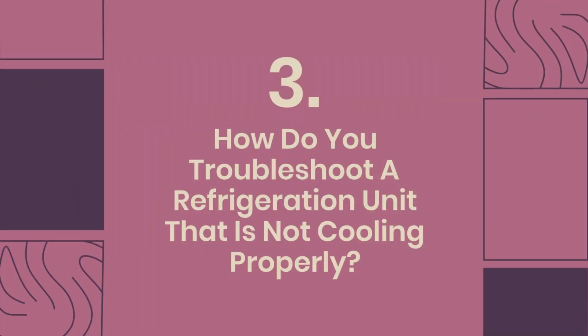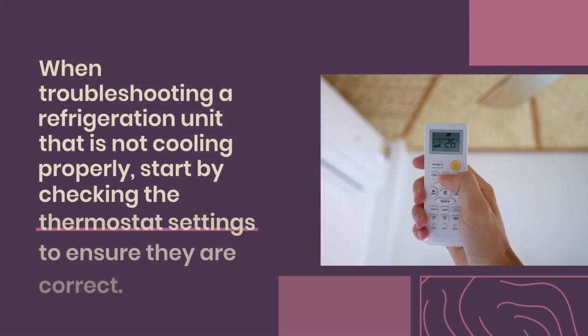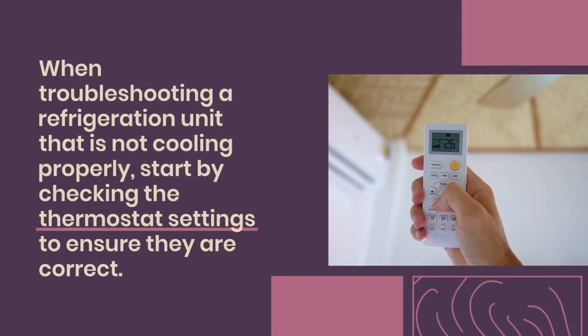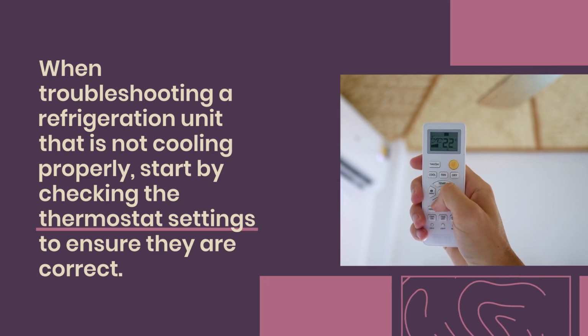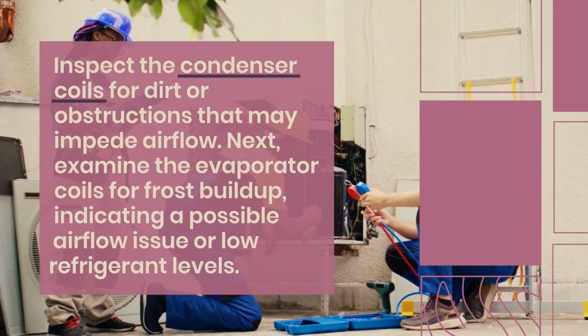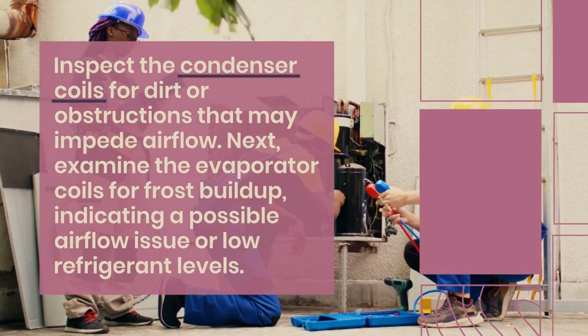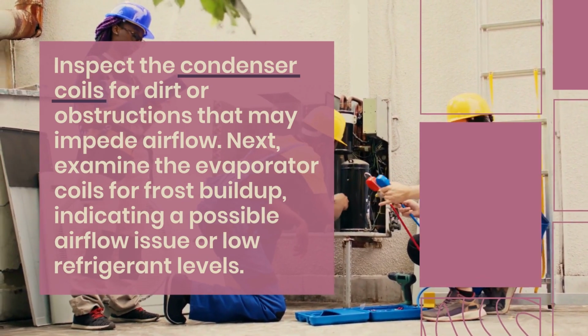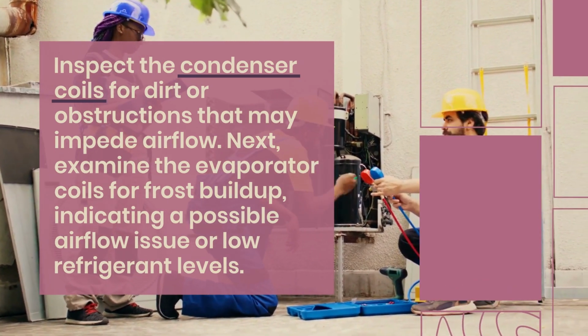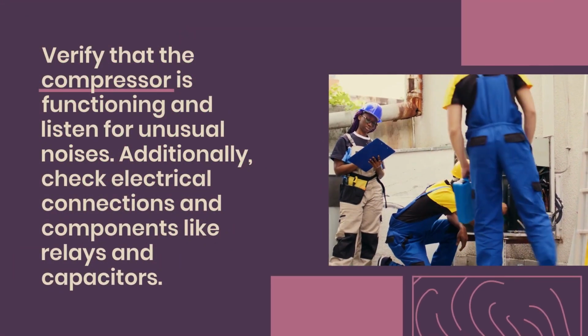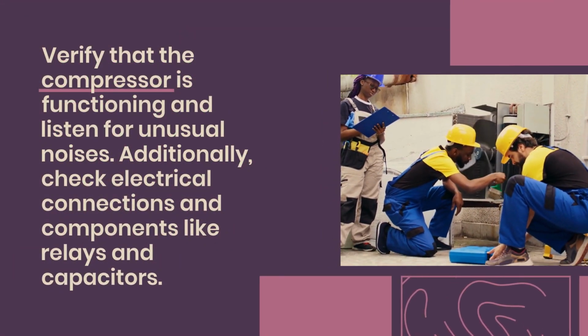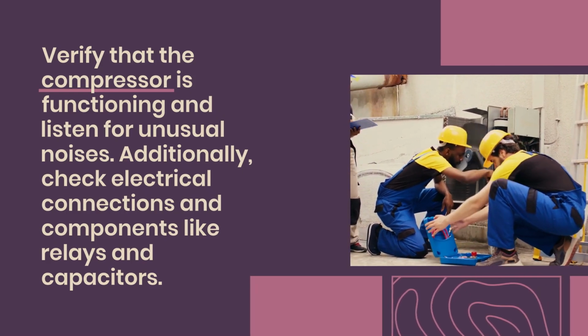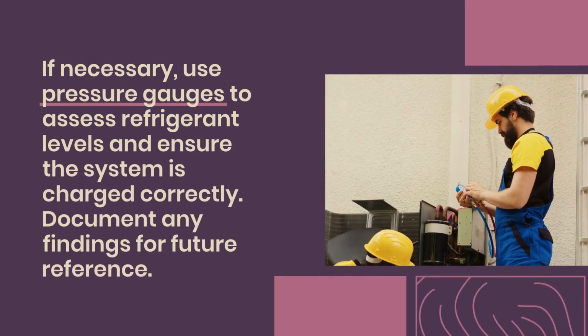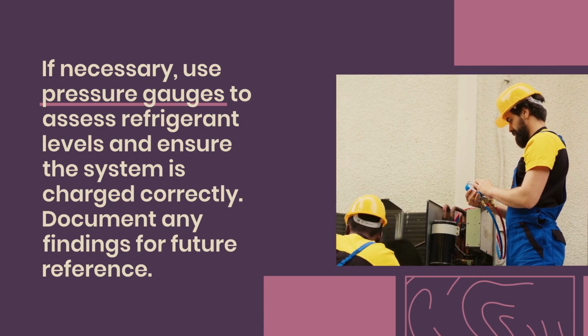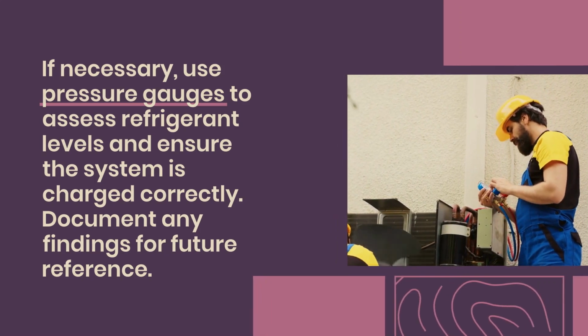3. How do you troubleshoot a refrigeration unit that is not cooling properly? When troubleshooting a refrigeration unit that is not cooling properly, start by checking the thermostat settings to ensure they are correct. Inspect the condenser coils for dirt or obstructions that may impede airflow. Next, examine the evaporator coils for frost buildup, indicating a possible airflow issue or low refrigerant levels. Verify that the compressor is functioning and listen for unusual noises. Additionally, check electrical connections and components like relays and capacitors. If necessary, use pressure gauges to assess refrigerant levels and ensure the system is charged correctly. Document any findings for future reference.